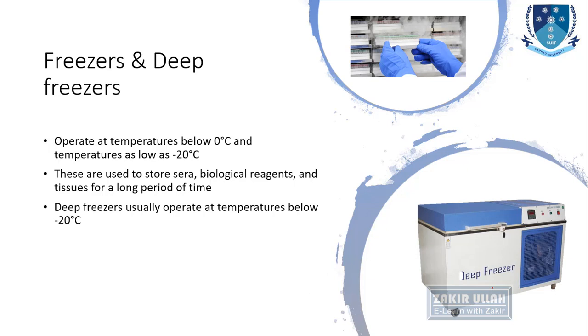Deep freezers used in the laboratory operate below a temperature of minus 20 degrees centigrade, and they can maintain a minimum temperature of up to minus 80 degrees centigrade.